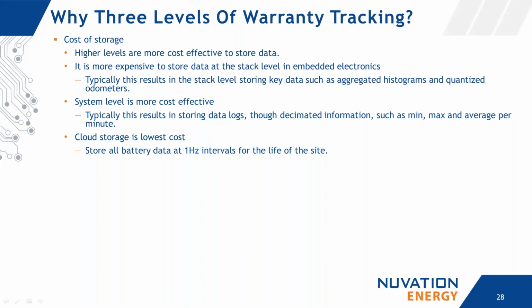At the system level, there's usually a ruggedized computer and storage is more cost effective, resulting in data logs. Typically there isn't enough room to store full 1 hertz information for the life of the site, so it's usually decimated: you take the 1 second data for a while, then decimate it down to minutes, and sometimes down to hours. Inside that decimation, you typically keep the min, max, and average, so you retain the limits of what happened inside the system.